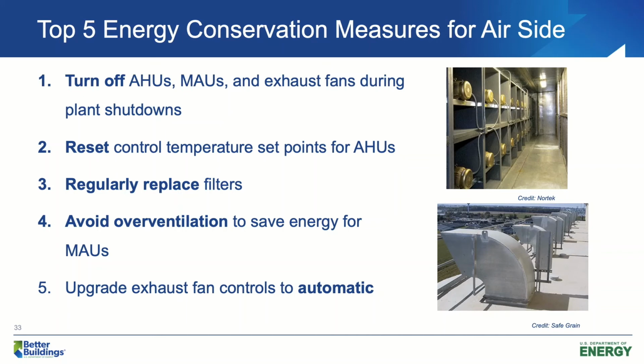Right here, I would like to summarize the energy conservation measures that we just talked about for the air side. Can we turn off air handler units, makeup units, and exhaust fans during plant shutdowns? If we cannot turn them off, can we reset the temperature and humidity set points? This way our equipment will not have to work as hard. Regularly replace the filters and avoid over-ventilation of our spaces to save energy. Upgrade all manual controls to automatic controls for exhaust fans.